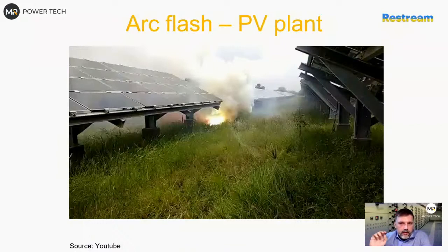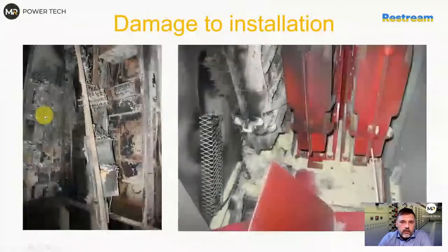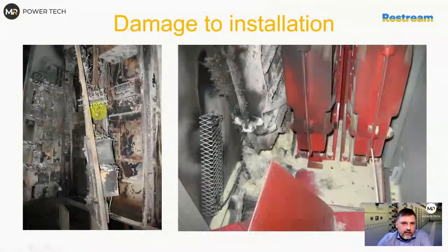If you have a small distribution board like a panel board, when you open it, maybe I can have a slide somewhere here. Wait a minute, yeah, it's damaged, but as an example. If you open it, you see the whole panel with cables in, cables out, all the equipment, control equipment. Then generally your line side is the energy for the whole panel. Despite some difference between bus and line, you take the line side as the worst one, because you can see everything there, and there is a big chance that this thing may happen.